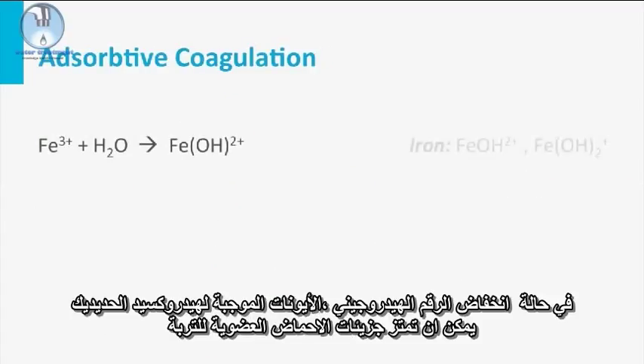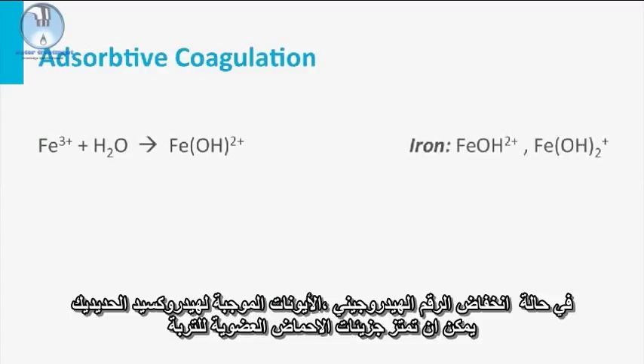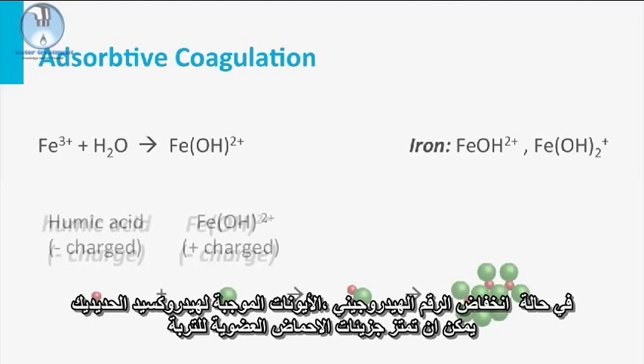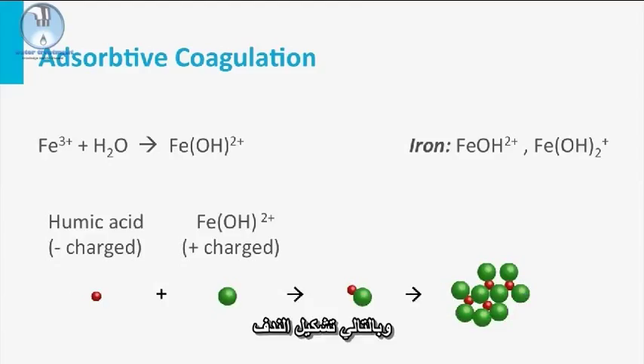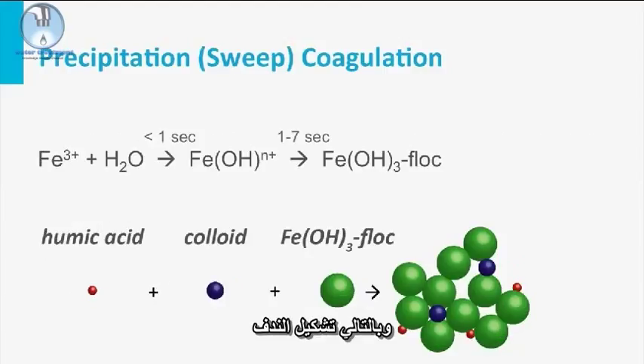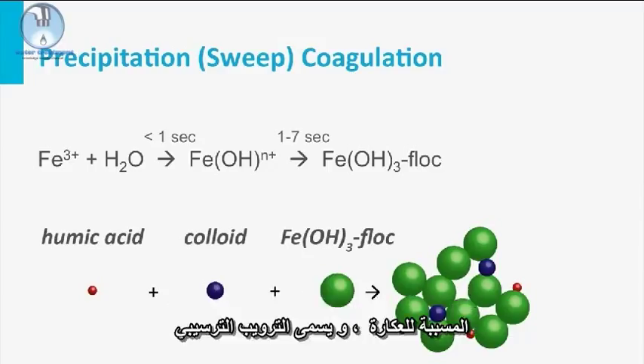At low pH, the positive ferric hydroxide ions can be adsorbed onto humic acid molecules, thus forming flocs. Finally, ferric hydroxide can precipitate, forming large meshes that can capture turbidity-causing particles — so-called sweep coagulation.